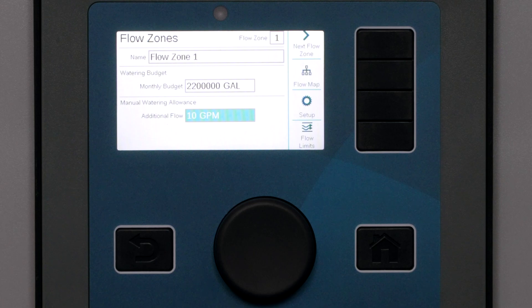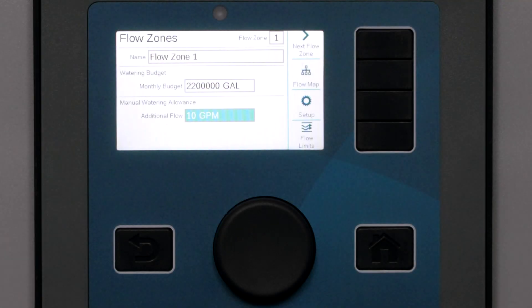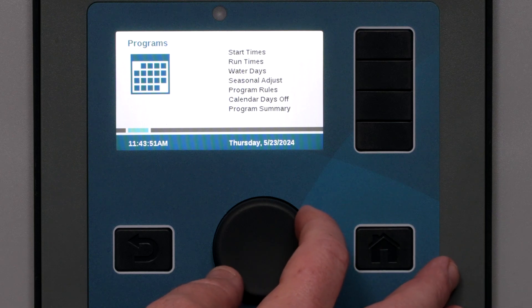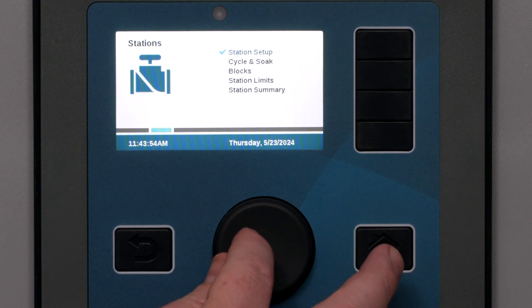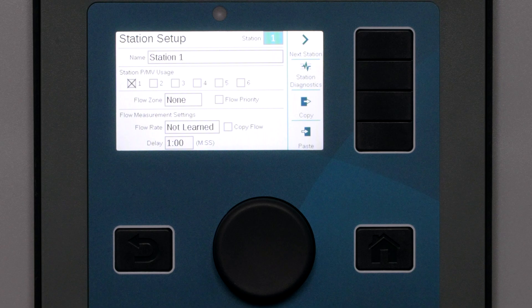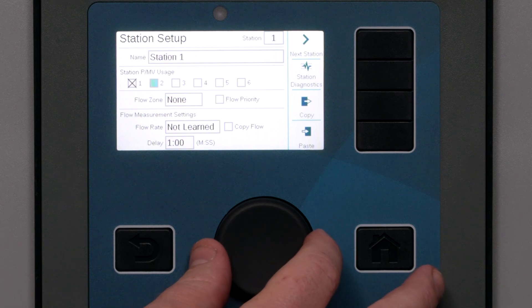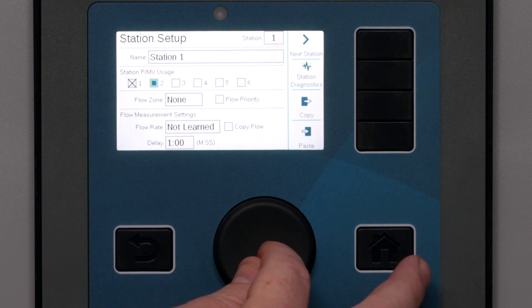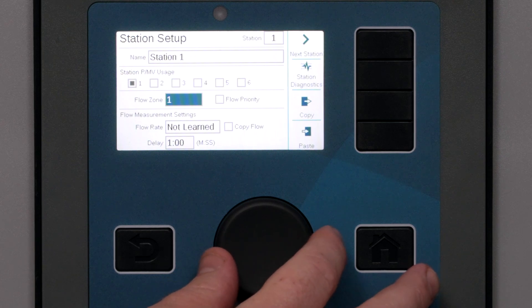That completes the initial setup for a flow zone. The next step is to add the individual stations to the flow zone. Go to the stations menu and select Station Setup. You must specify the flow zone for each station in the system — in effect, this attaches them to the mainline pipe being monitored. Even if you only have one flow zone, this must be filled in for flow monitoring to work properly. We'll attach the first station to flow zone 1 by selecting that in the flow zone field.